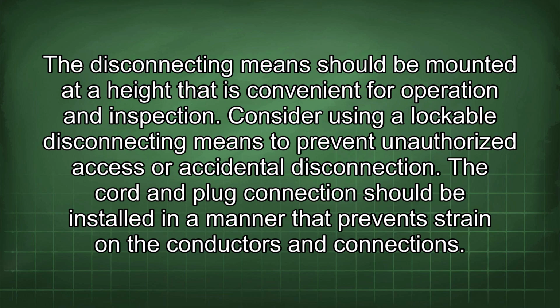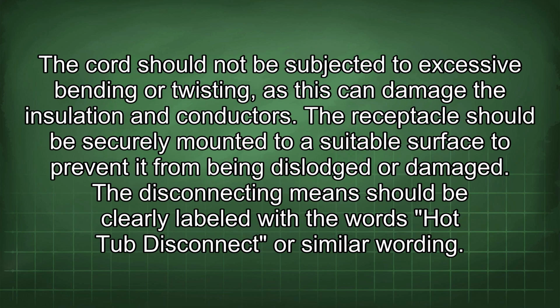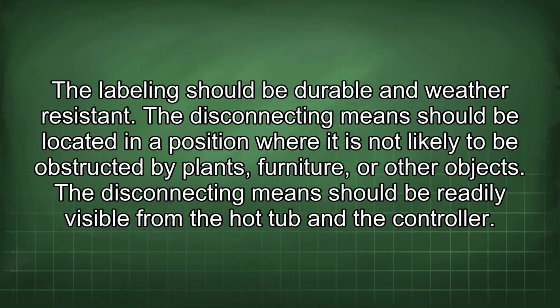The cord and plug connection should be installed in a manner that prevents strain on the conductors and connections. The cord should not be subjected to excessive bending or twisting, as this can damage the insulation and conductors. The receptacle should be securely mounted to a suitable surface to prevent it from being dislodged or damaged. The disconnecting means should be clearly labeled with the words "hot tub disconnect" or similar wording. The labeling should be durable and weather resistant.